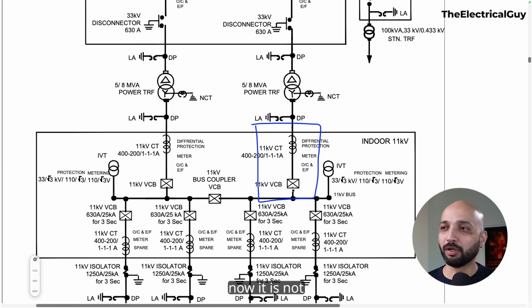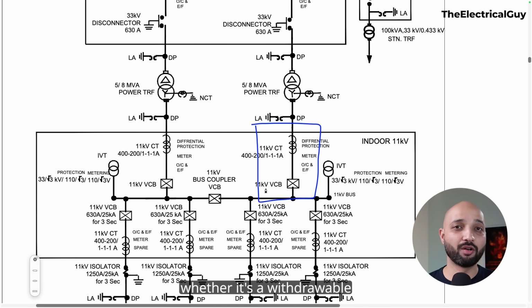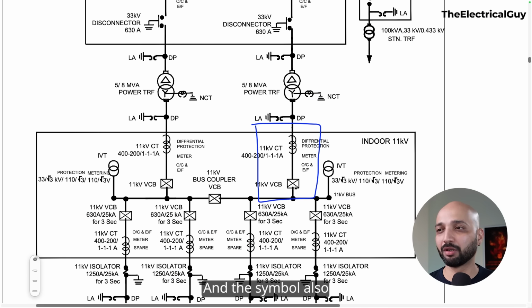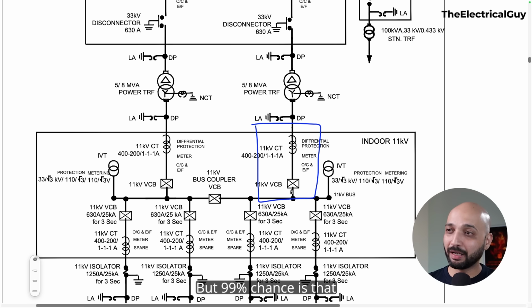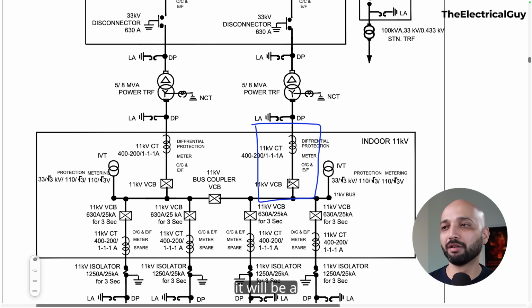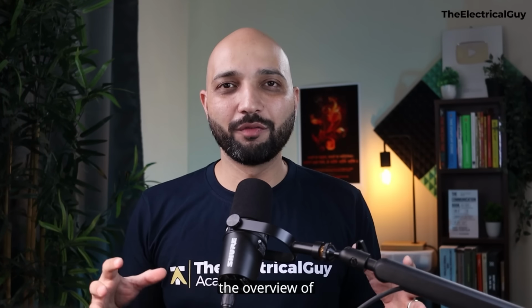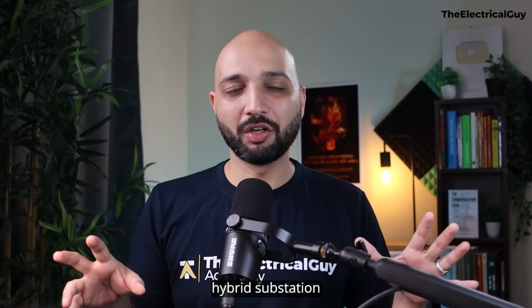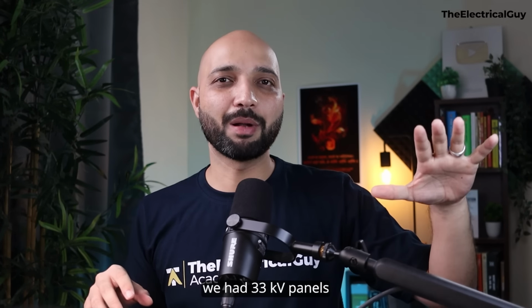Now it is not clearly mentioned here whether it's a withdrawable type or not, and the symbol also does not specify that, because for the withdrawable type we have a dedicated symbol. We discussed that in the SLD masterclass course. So that is also not clear, but there is a 99% chance that it will be a withdrawable type circuit breaker, and that's why no isolator is used. Clear? So that is the overview of the 33 by 11 kV hybrid substation, where we saw we had 33 kV panels with GIS and 11 kV panels with AIS.